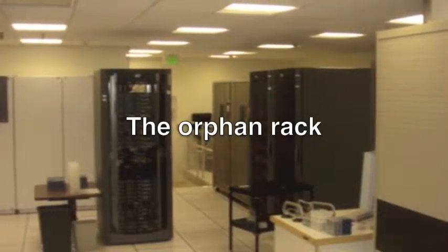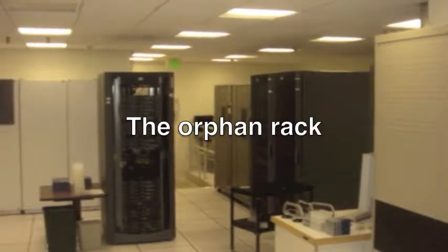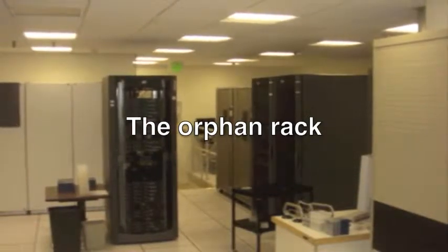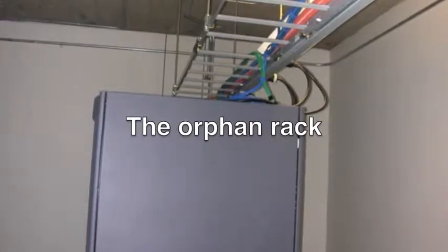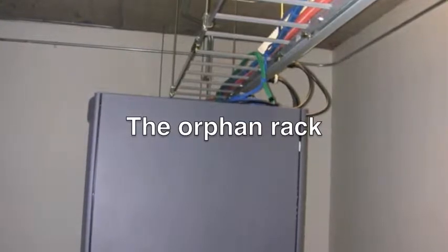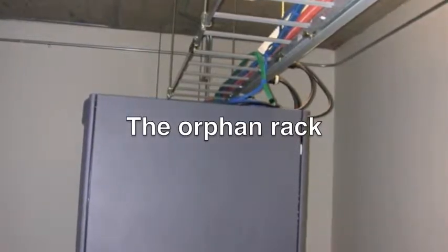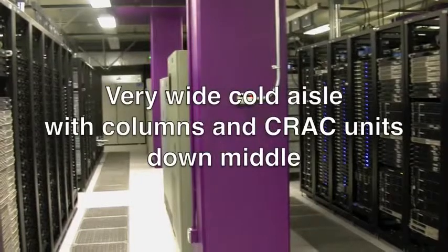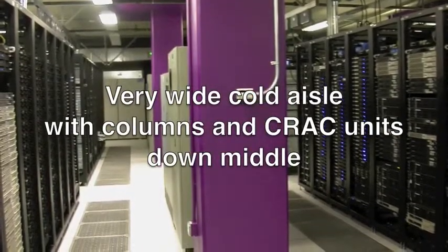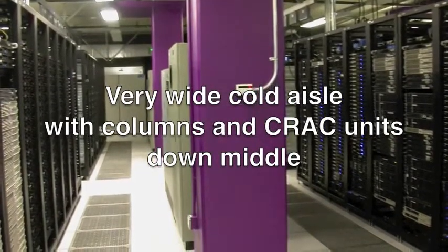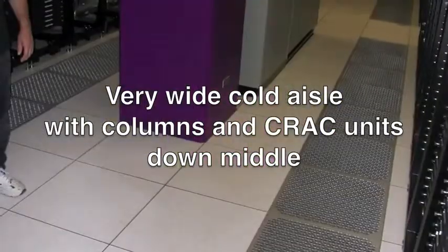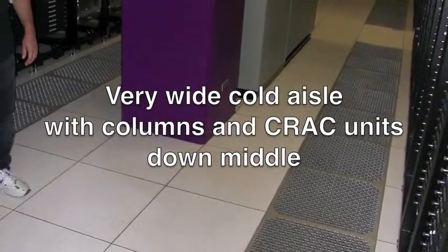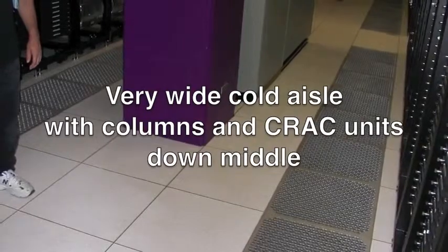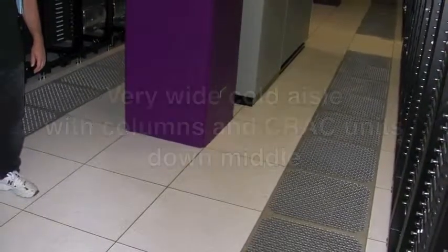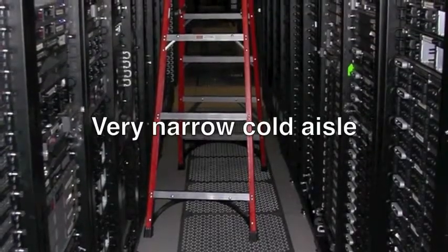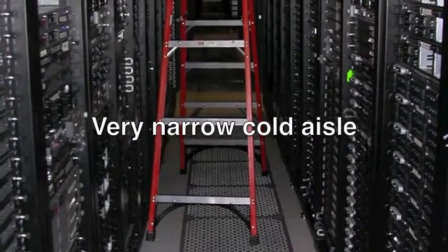The orphan rack is a situation where you have a single rack or a couple racks all by themselves, and again, we have to figure out if and then how we're going to contain those. Here is a particularly difficult area to contain because it's a 10, 12-foot aisle, plus there are columns and air conditioners in the middle of the aisle, so that one's pretty complex. And opposite of the wide aisle is sometimes you get very narrow aisles, and those can actually be a bit easier to contain.